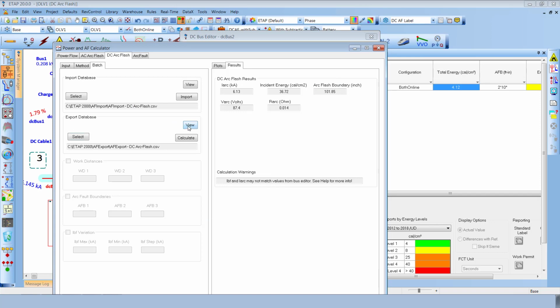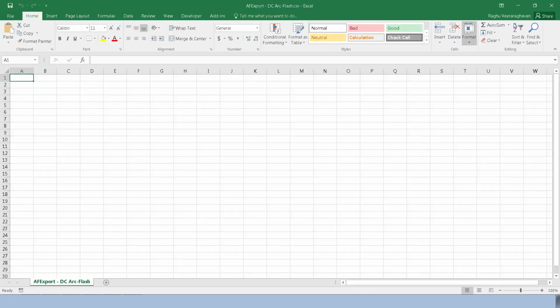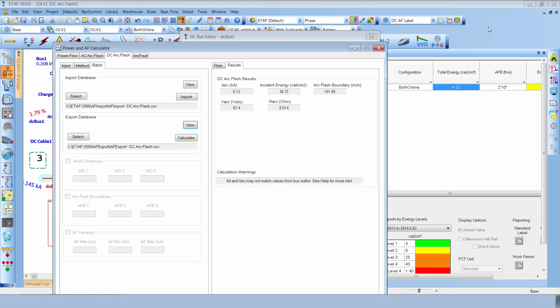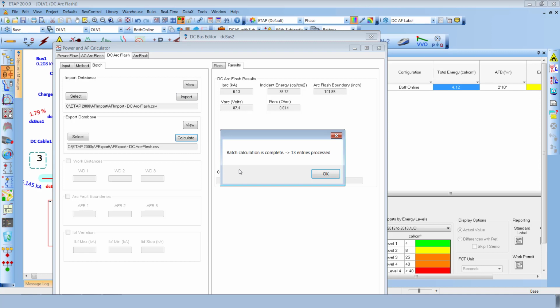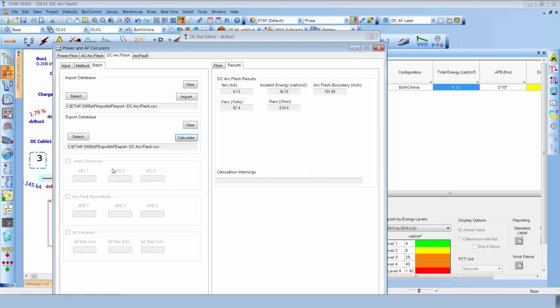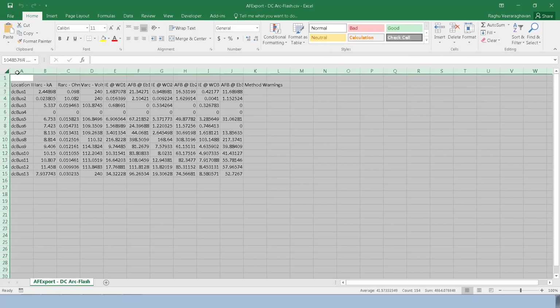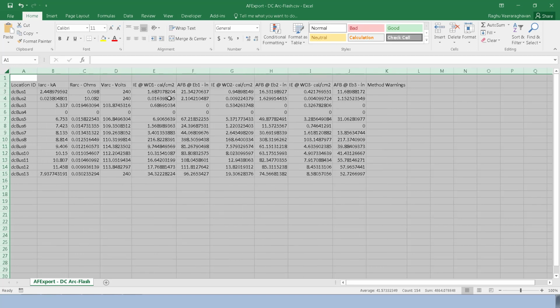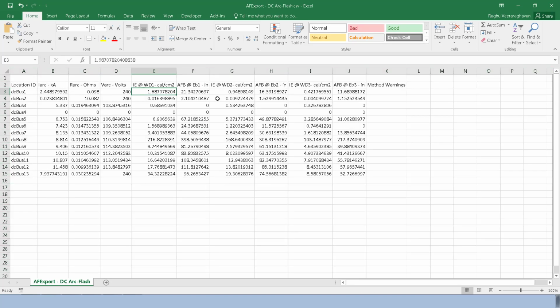Before running the import process and the export process, you can notice here that the Excel sheet is blank, and once the import process is complete, the user can simply run a calculate button and process as many batch entries as they want, and still evaluate the working condition and the final incident energy based on each working distance and the corresponding arc flash boundary accordingly.